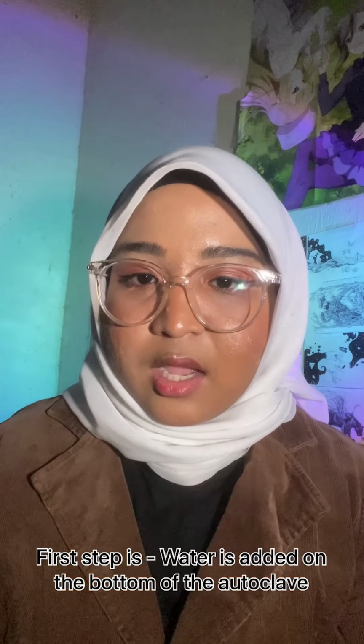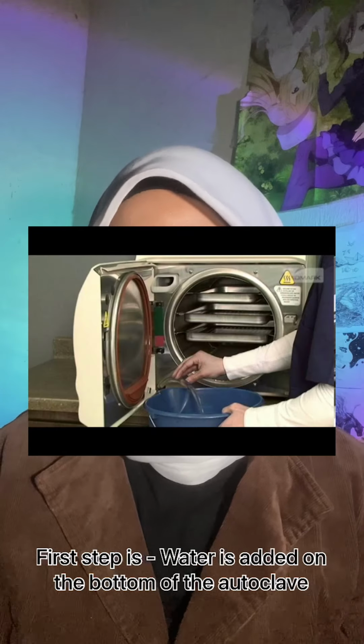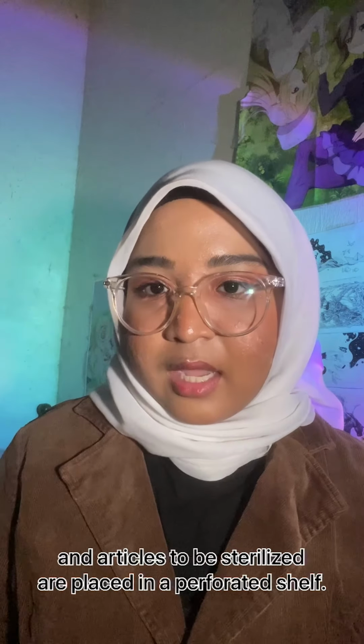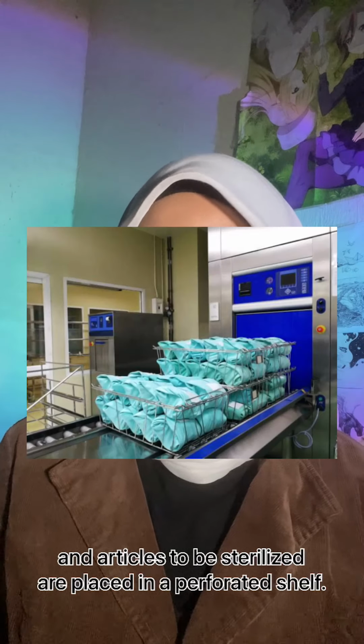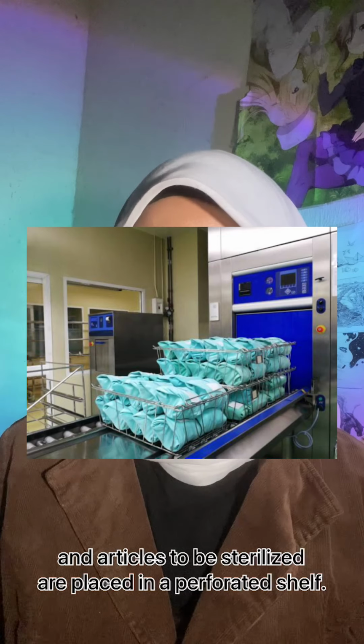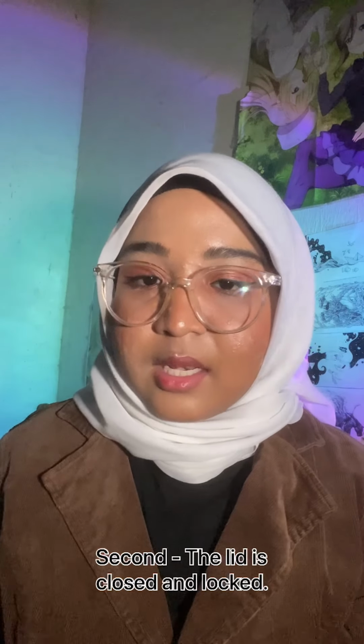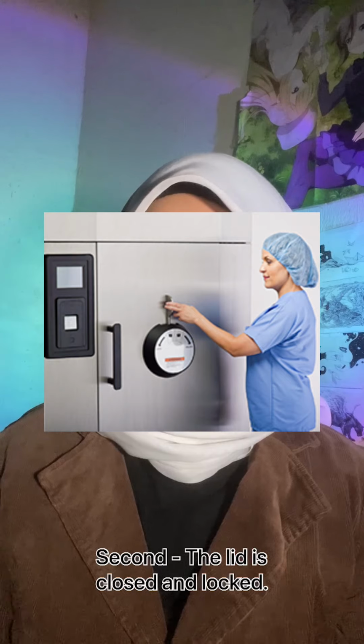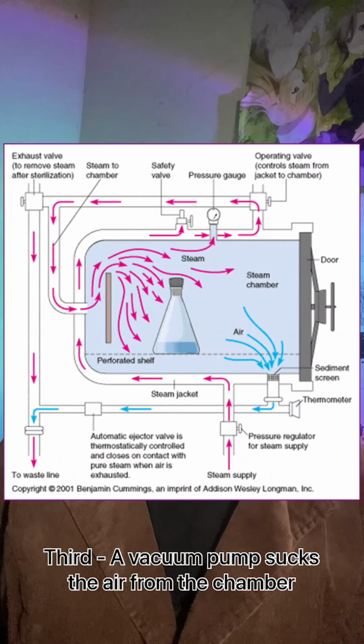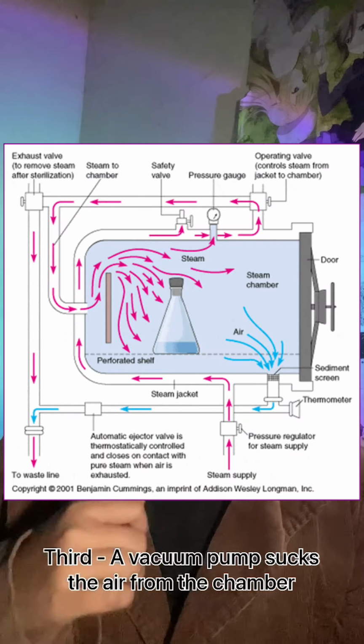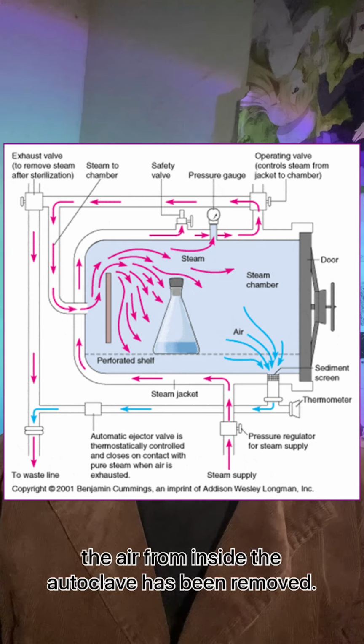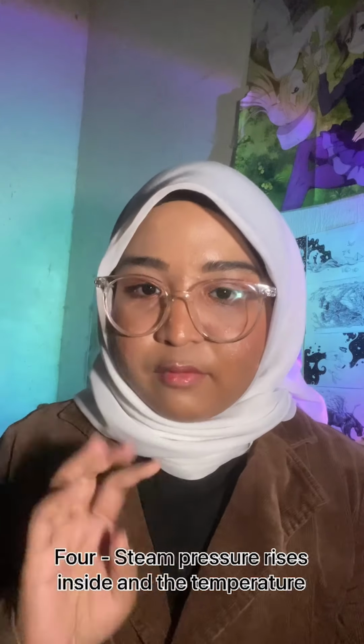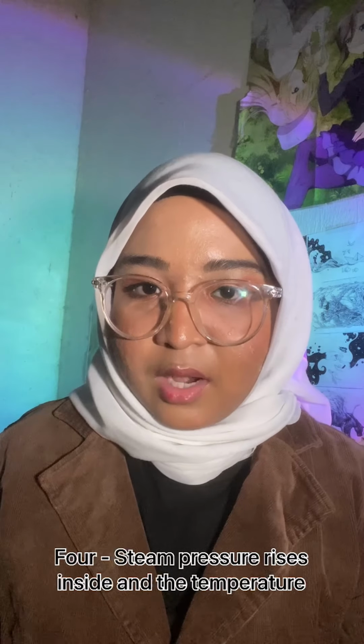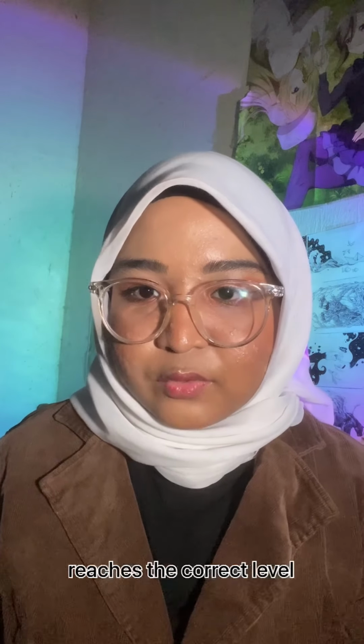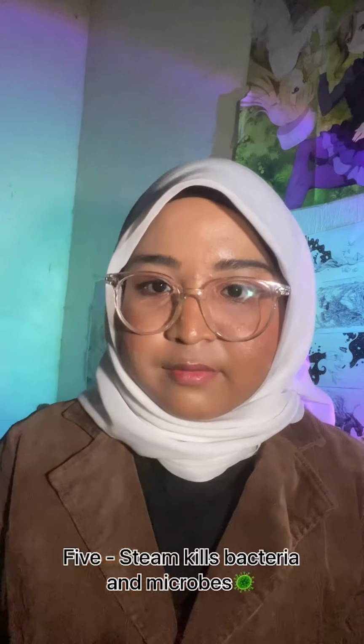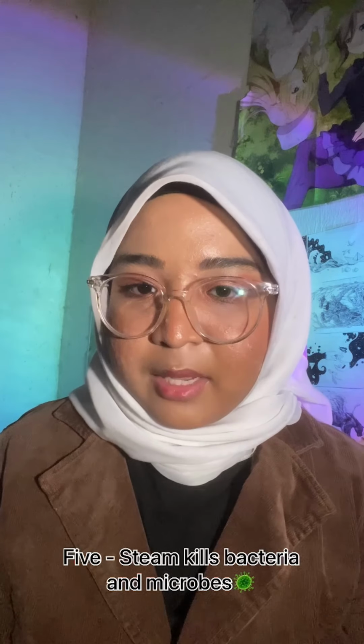First step, water is added to the bottom of the autoclave and the articles to be sterilized are placed on a perforated shelf. Second, the lid is closed and locked. Third, a vacuum pump sucks the air from the chamber and the air inside the autoclave is removed. Fourth, steam pressure rises inside and the temperature reaches the correct level. Fifth, steam kills bacteria and microbes.